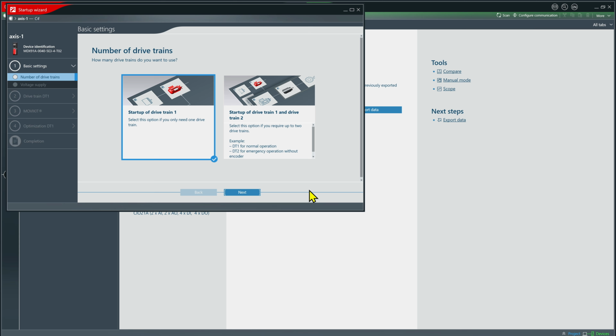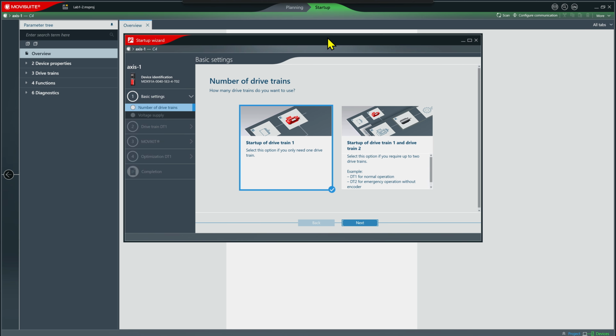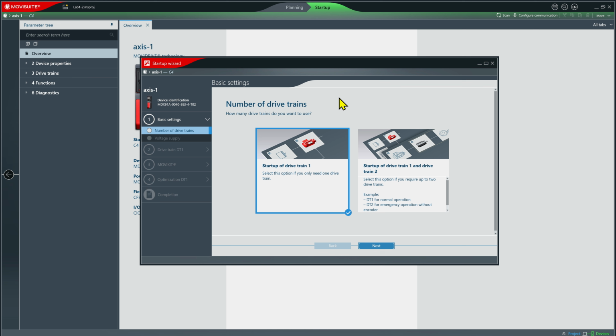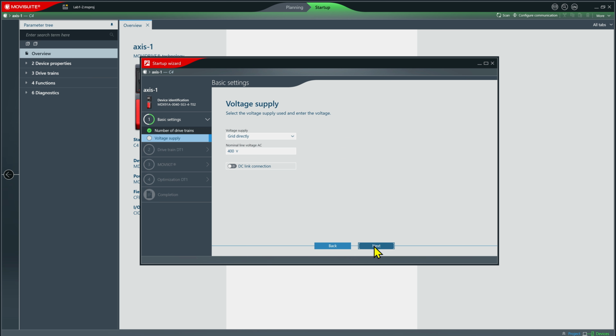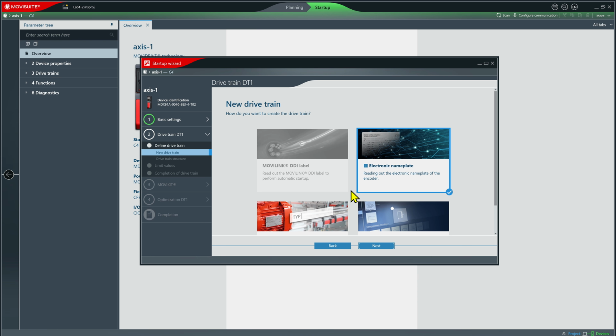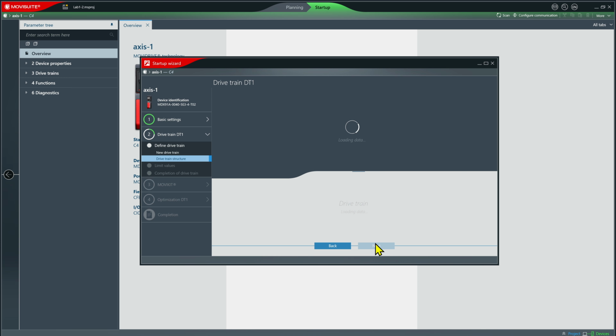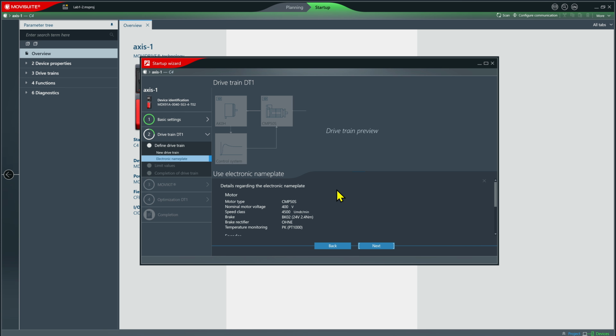Okay, that's complete. And now the Startup Wizard window opens up here in the middle. It's a separate window actually. And it says, do we want to start up drivetrain 1? And I say, sure thing. Click Next. What voltage do you have? 460. Enter that in. Click Next. Do I want to use the electronic nameplate? All right, we didn't use it last time. Let's use it this time just so you can see how it works. So I pick electronic nameplate, I click Next. It shows me my motor settings, and I'm going to just quickly eyeball them to confirm they're correct, and they look fine to me. So I'll click Next.